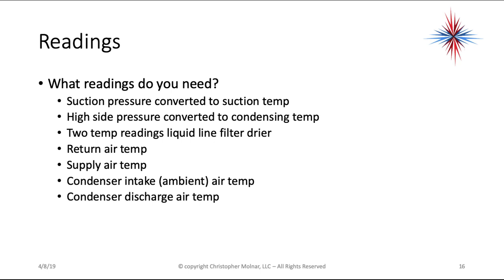So what readings do you need to do this? Basically you're taking eight readings: suction pressure converted to suction temperature; high side pressure converted to condensing temperature; two temperature readings at the liquid line filter dryer — one before and one after — make sure those thermometers are calibrated correctly; return air temperature; supply air temperature; condenser intake ambient air temperature (watch the sunlight); and condenser discharge air temperature right on top of the fan — but make sure you don't drop your probe into the fan. Again, these are rules of thumb. You do not want to use these for a full diagnosis, but this is a great way to get started, and in an emergency or quote situation, this is where you would start.